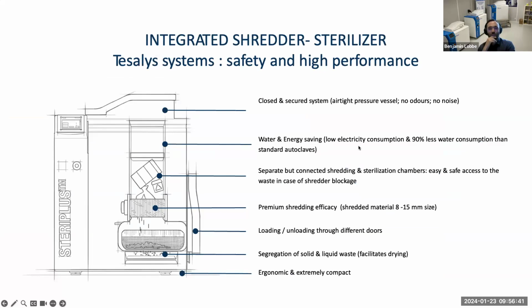So we have here the SteriPlus unit. To explain quickly before displaying the video, the waste is loaded from the top, both solid and liquid waste, including sharps, PPE equipment, vaccine bottles, metal, glass, plastic, and liquid waste as well. Then the machine will close, and we have first a shredding process. All the waste in the loading chamber will be shredded, cut into small pieces of 1 centimeter maximum. Solid waste will fall down into the basket that we can see on the drawing, and liquid waste will fall down at the bottom of the unit. So there is a segregation between liquids and solid waste.